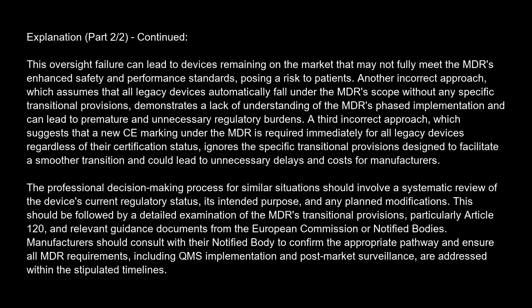The professional decision-making process for similar situations should involve a systematic review of the device's current regulatory status, its intended purpose, and any planned modifications. This should be followed by a detailed examination of the MDR's transitional provisions, particularly Article 120, and relevant guidance documents from the European Commission or notified bodies. Manufacturers should consult with their notified body to confirm the appropriate pathway and ensure all MDR requirements, including QMS implementation and post-market surveillance, are addressed within the stipulated timelines.